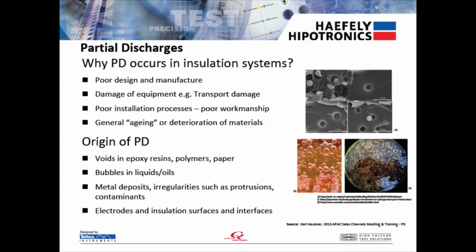So partial discharge. One of our biggest recommendations for testing is PD testing, partial discharge testing. Partial discharge is when there isn't a complete discharge or flashover within the unit, but there are small pockets in the insulation, paint, oil, and they essentially charge up and discharge.